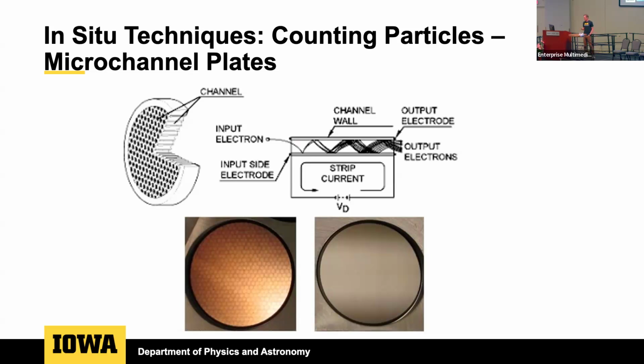So this microchannel plate that you're looking at here is about life size on the computer screen. It's a couple inches across here. You can see the individual microchannel plate tubes in there. So this is the top view of something that looks like this in cross-section, which has a whole bunch of individual tubes going through here. So if you put one of these things as a detector, a particle comes in, and if it hits one of the open pores, it'll knock an electron off of there, create a cascade, and by the time you get to the bottom, you've got your 1,000,000 electron pulse that you can register with your electronics.